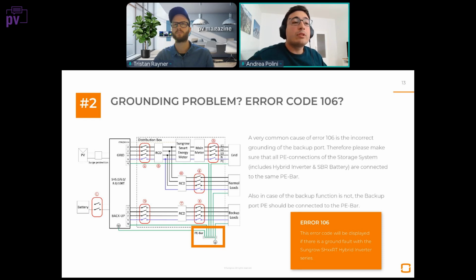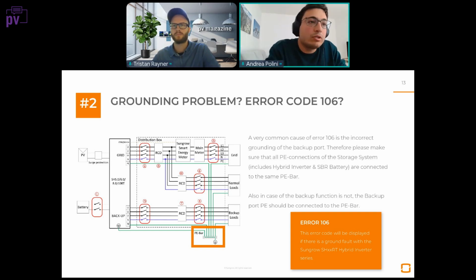So when the grounding is improper, the error 106 will happen. This error is happening when we are checking for voltage difference between the neutral line and the grounding line, and we are seeing some variation of more than 30 volt, and this is when we show the error 106. However, it could happen that the error is not shown, and still the backup function doesn't function correctly. And one of the main culprits that we have found is indeed the missing of the grounding of the installation.